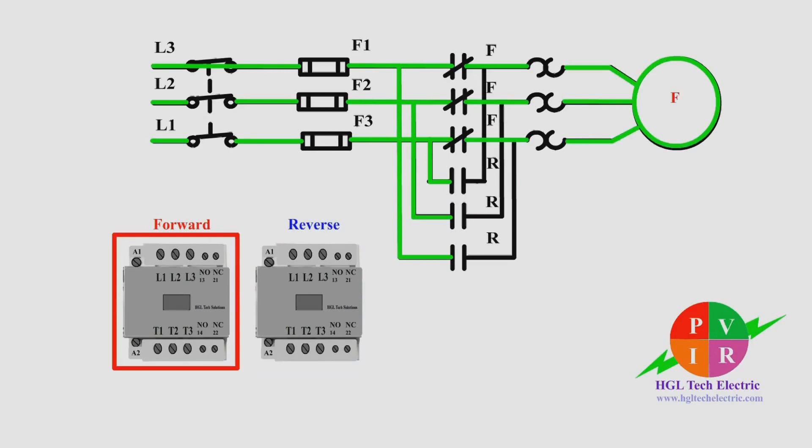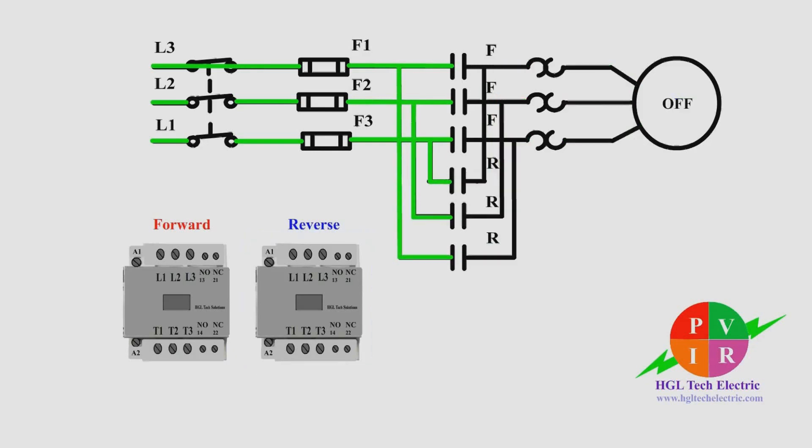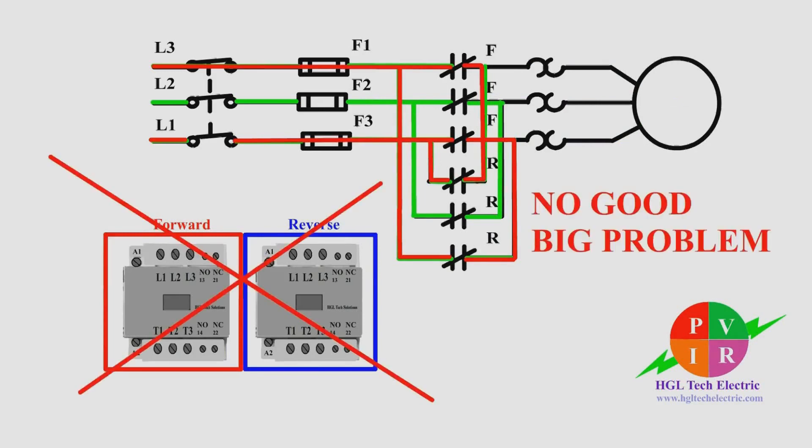We will use two separate contactors and an overload relay to selectively energize the three-phase motor. That seems simple, however if accidentally both contactors are energized at the same time, that would be a big problem. That should never happen because it would be shorting out two of the lines.